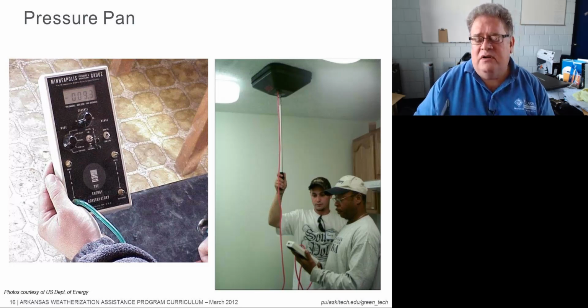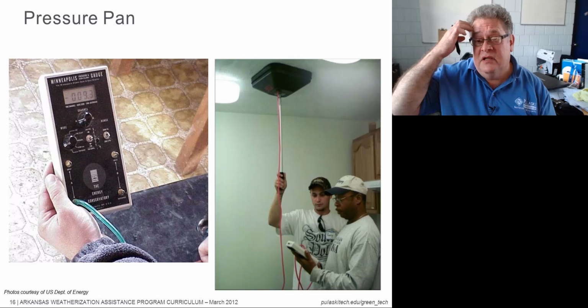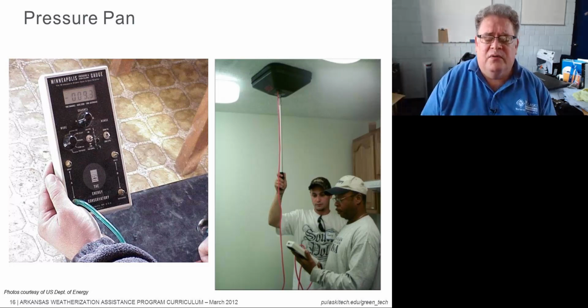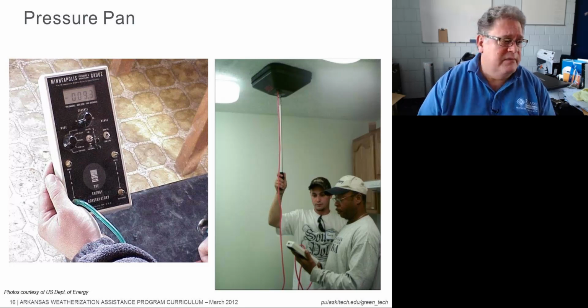You don't have to buy one that's fancy like this one. It's made by the Energy Conservatory, the same people that make the Minneapolis blower door and that gauge on the left. You can use a cake pan with a pressure tap in it. Basically just a hole to stick a hose in. Just make sure the hole is airtight, that you put some weather stripping around it, put some kind of handle on it. Here they've got just a metal stick on it.